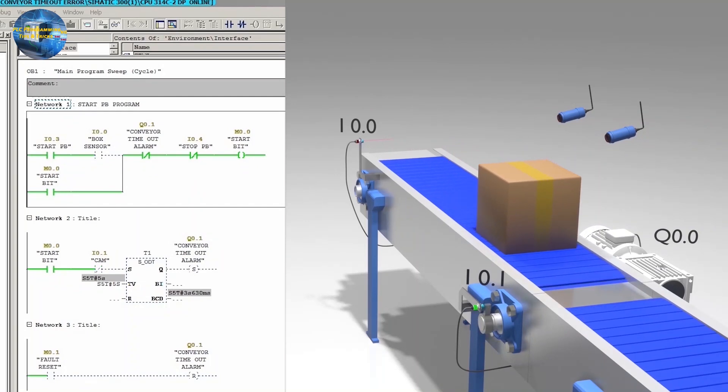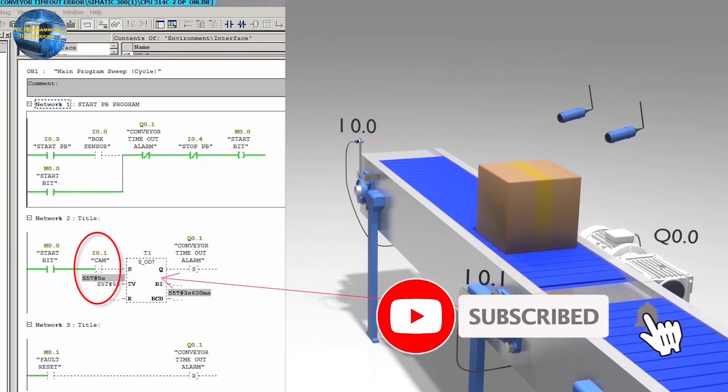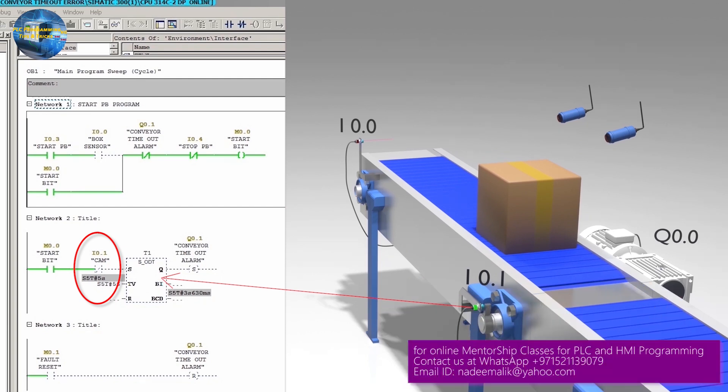But what if the conveyor belt fault occurs and it stops when the cam is right in front of the sensor I0.1? As we have used the normal close contact of the sensor I0.1, when the cam is in front of this sensor, this normal close contact will get opened up and it will disable the timeout timer.